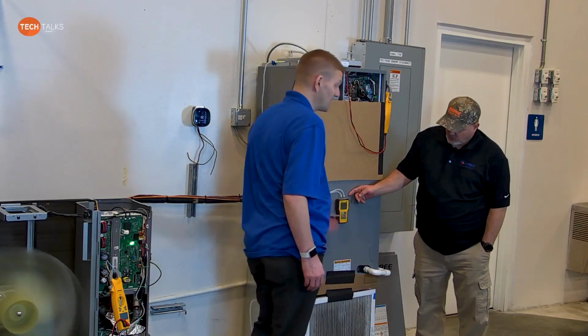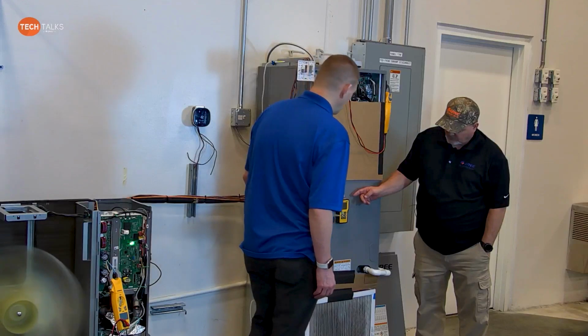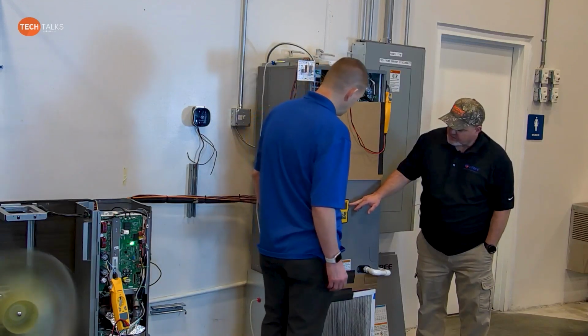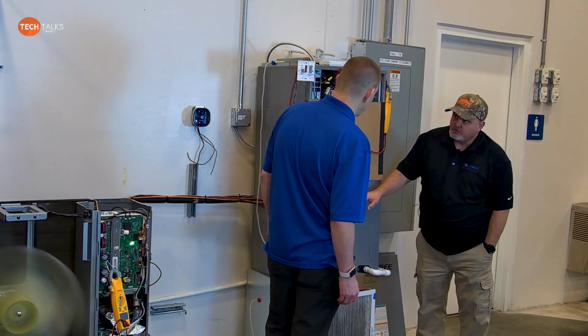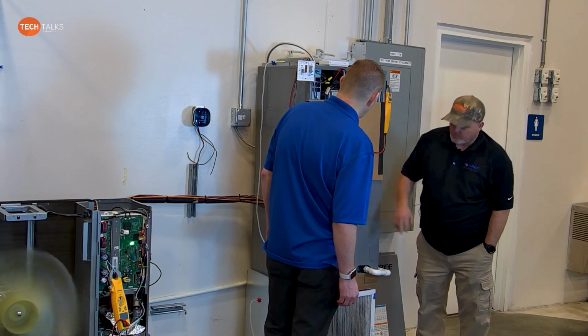3 and 4 were off. So that's the factory default level setting for the 3-ton air handler, okay? We got the Magnehelic gauge set up. Let's see what kind of static we're running. As you can see, we are including the filter in this demonstration. That's why we pulled it out and put it on the front. Did you disconnect this and zero it? Yes. Okay, cool.